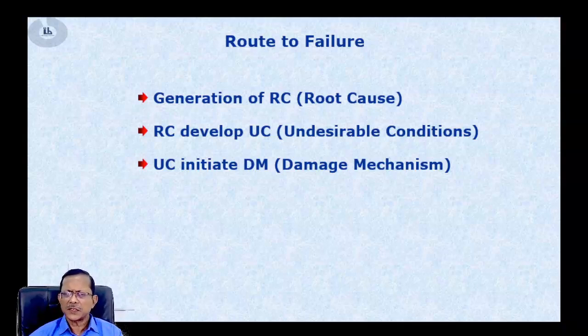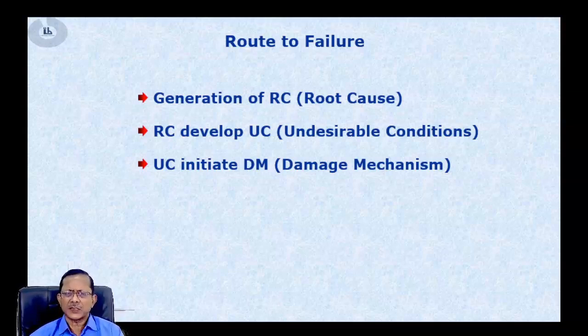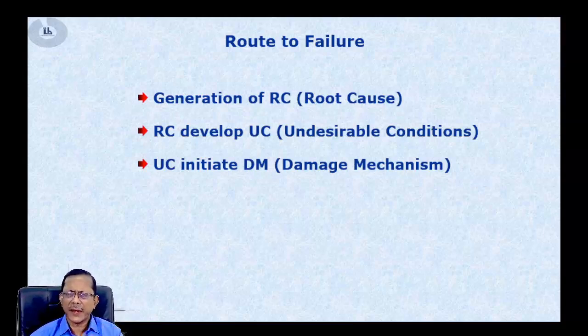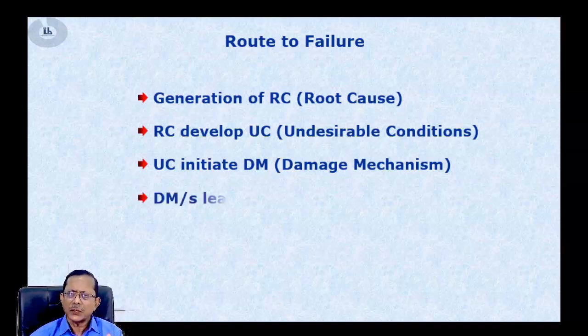That undesirable condition initiates a damage mechanism. Damage mechanisms very seldom lead to instantaneous failure — that is very rare. There are a few aggressive damage mechanisms, such as secondary steam jet erosion, where a failing superheater coil puts surrounding tubes in imminent danger due to very fast erosion, but those are rare.